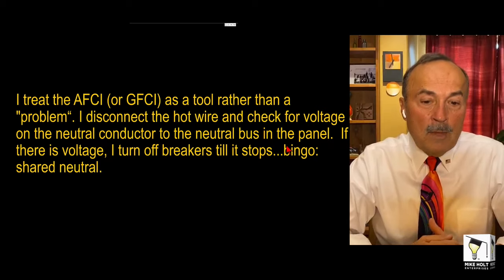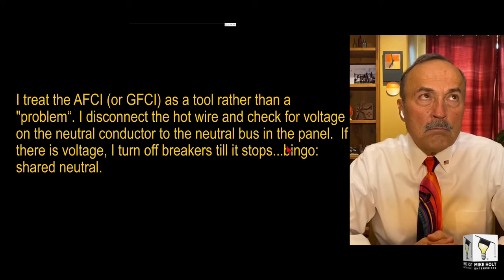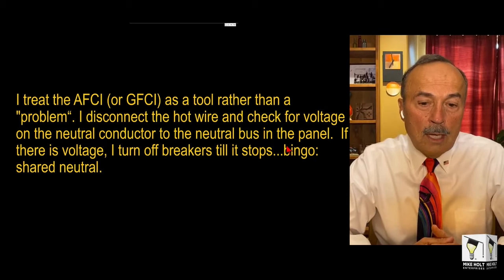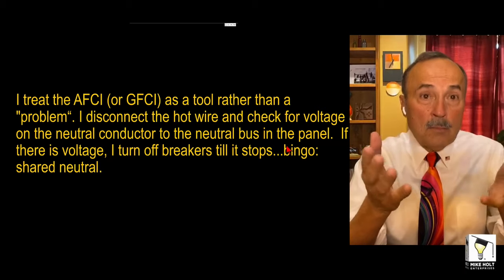He says, here's what I do. I disconnect the hot wire. Even though you have an AFCI, it tripped. So what I do is I disconnect the hot wire off that AFCI that's tripping, and check for voltage on the neutral conductor to the neutral bus in the panel. In other words, I see this hot wire has this neutral. Then I take the hot wire off of the AFCI, and I check the voltage of that neutral conductor at the panel to the neutral bus.